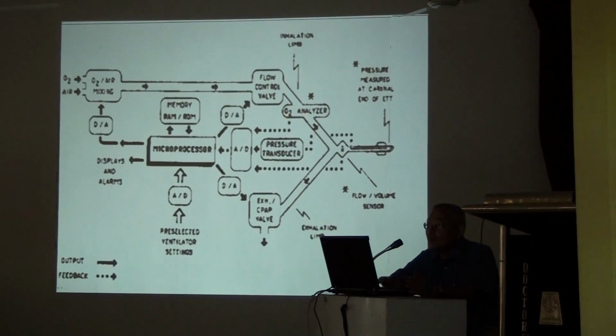What will this sensor do? This is a flow sensor. The flow sensor may be here, or it may be here. If it is a single limb circuit, the flow sensor will be at this position. If it is a twin limb circuit, the flow sensor will be at the outlet. Why the international dictum, as the ISO organization has said, of oxygen analyzer in this position and flow sensor at this position?